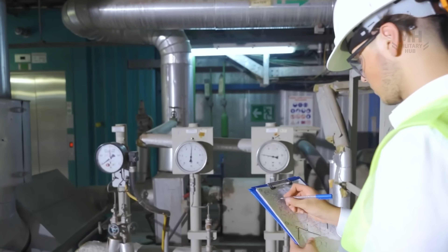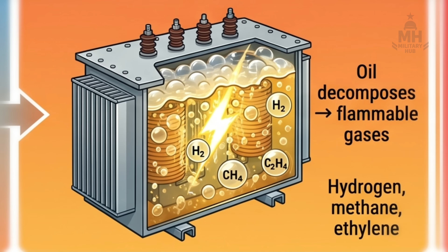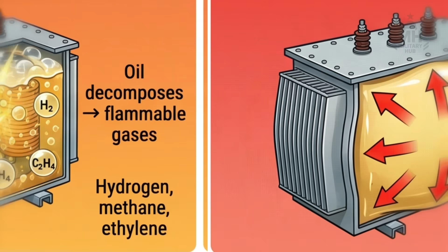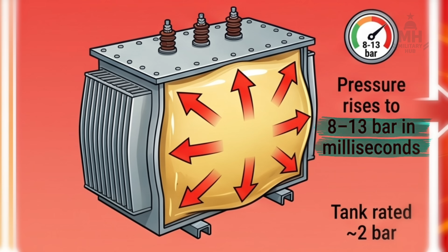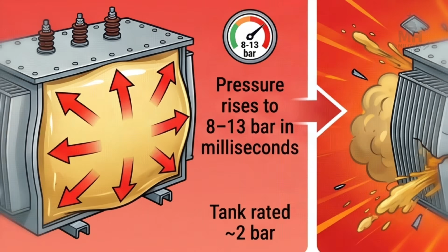That is what happens in an oil-filled transformer explosion. The physics are well understood, even if the results are spectacular. When an internal fault, typically an electrical arc, occurs inside the sealed tank of a large power transformer, it rapidly decomposes the mineral oil that acts as both coolant and insulator. This decomposition generates enormous volumes of flammable gas, hydrogen, methane, ethylene, in milliseconds. The pressure inside the steel casing spikes from ambient to anywhere between 8 and 13 bar within 30 milliseconds. The tank, usually rated to withstand no more than about 2 bar of static pressure, ruptures violently. The oil, now exposed to oxygen and heated well past its flashpoint, ignites.